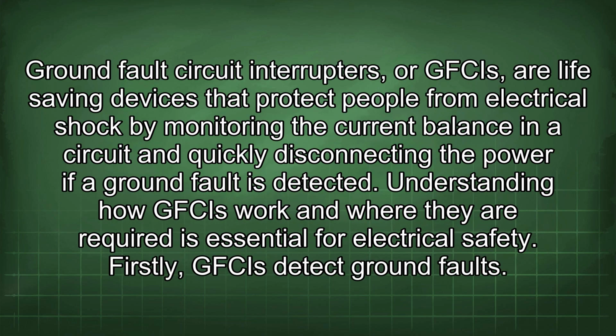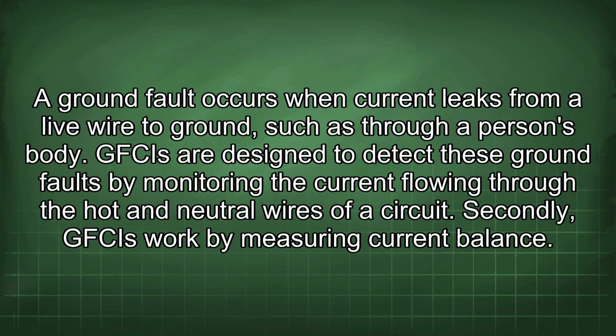Ground fault circuit interrupters, or GFCIs, are life-saving devices that protect people from electrical shock by monitoring the current balance in a circuit and quickly disconnecting the power if a ground fault is detected. Understanding how GFCIs work and where they are required is essential for electrical safety. Firstly, GFCIs detect ground faults. A ground fault occurs when current leaks from a live wire to ground, such as through a person's body. GFCIs are designed to detect these ground faults by monitoring the current flowing through the hot and neutral wires of a circuit.